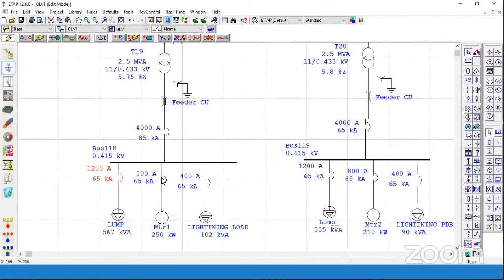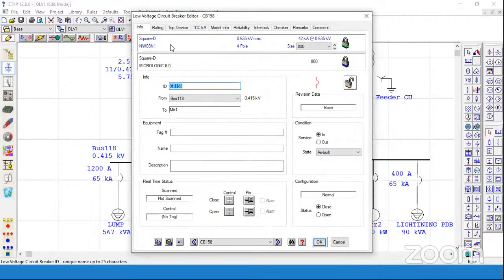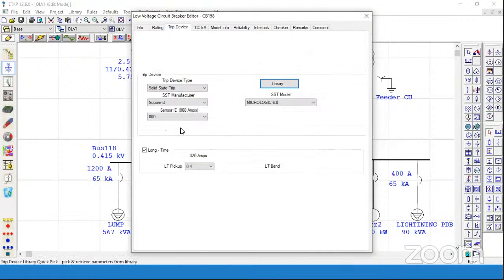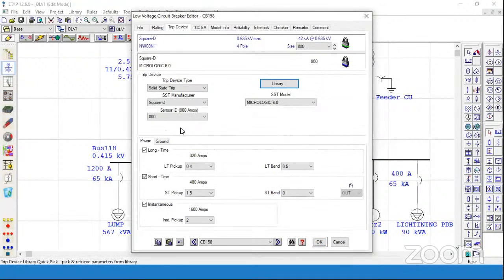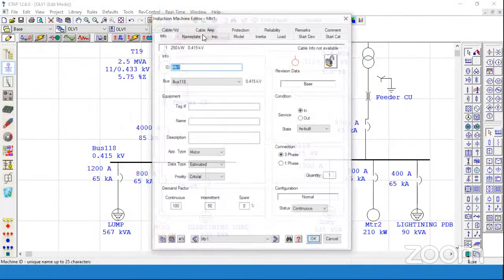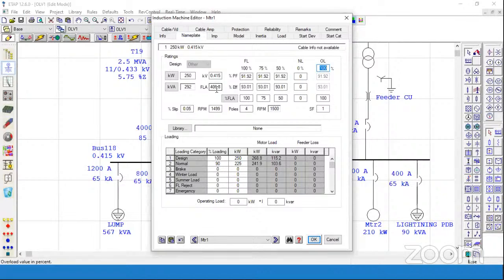Likewise, every parameter has been set for every feeder. For motor feeders, we have also given settings to the motor feeder, as you can see over here. Now let's set this motor feeder. The motor is rated 250 kilowatt. The full load ampere of this motor is 406 ampere.